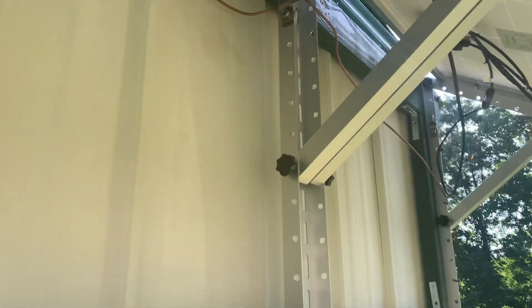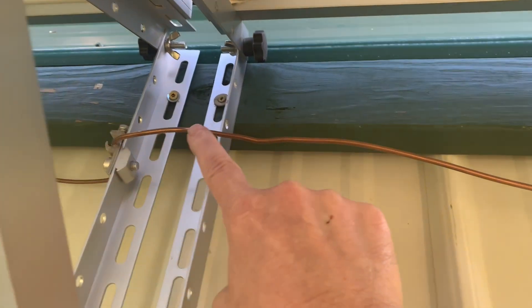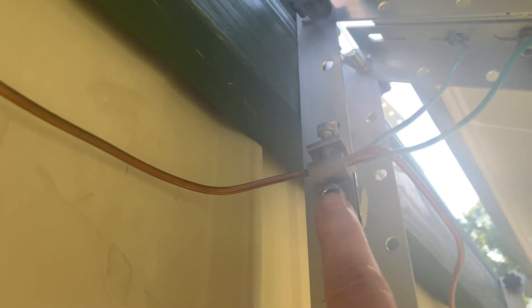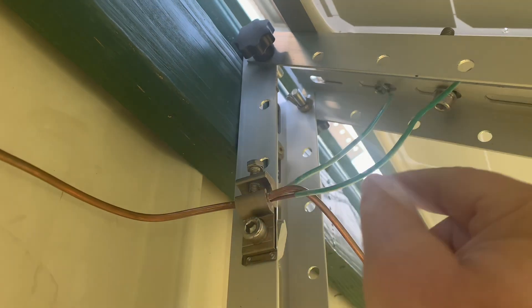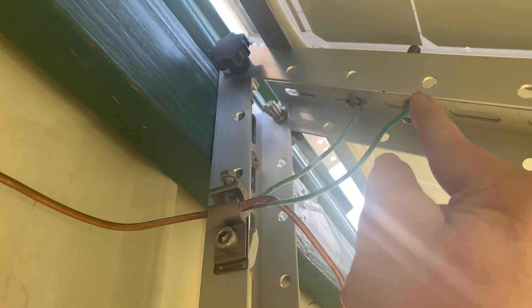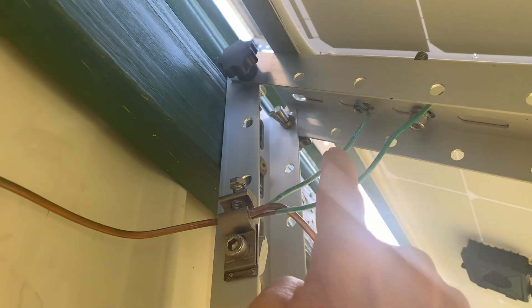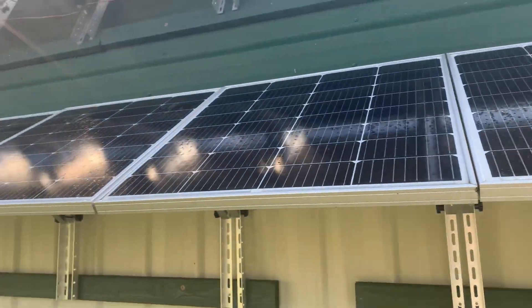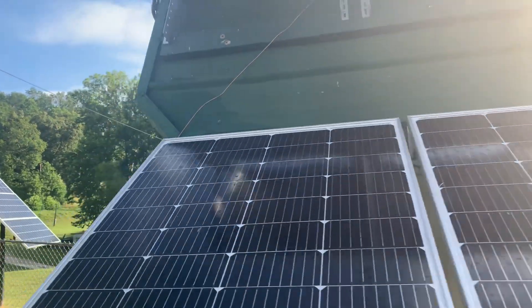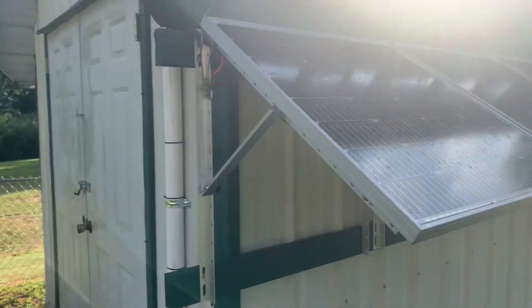If you look up under here, this stretches from — I put one lug in between two panels. You can see my lug here, I put it on the frame. The number six grounding wire goes through the lug, and then I took the pigtails and grounded them straight through the frame of the panel. Connected the open end right here — this one goes to this panel, comes down and goes in there, and you just screw it down tight. So these two panels are tightened up and grounded. I just did that on every other panel — the lug on every other one. You can see here where it drops down and goes all the way up through there.